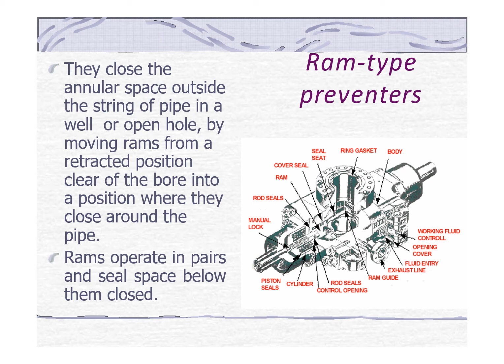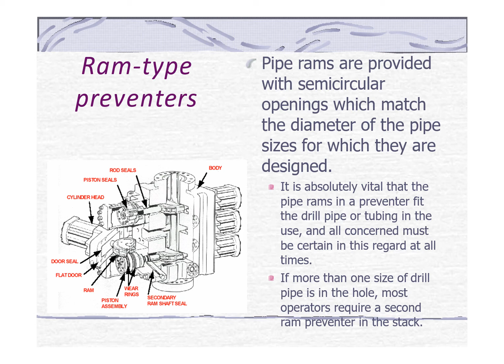Pipe rams are provided with semicircular openings which match the diameter of the pipe sizes for which they are designed. It is absolutely vital that the pipe rams in the preventer fit the drill pipe or tubing which is in use. If more than one size of drill pipe is in the hole, most operators require a second ram preventer in the stack.